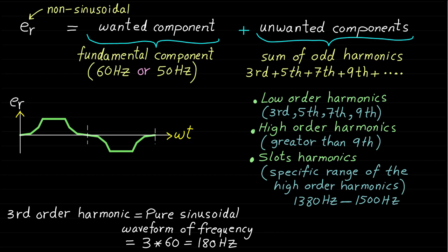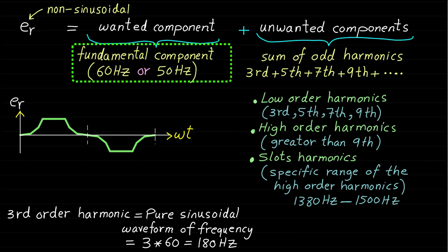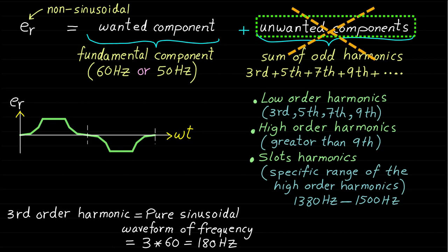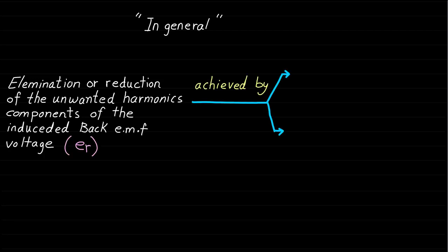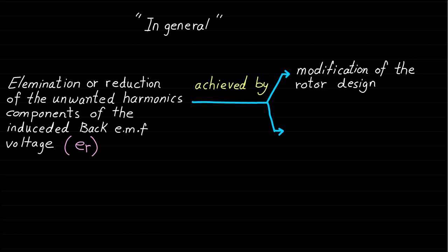We will give more detail about these harmonics during the discussion of the distributed windings. Now, pay attention to this important point. In practice, the armature back EMF induced voltage ER should ideally contain only the fundamental component with a frequency of 60 Hz or 50 Hz. Therefore, the unwanted harmonic components should be eliminated or reduced. In general, this elimination or reduction can be achieved by using two approaches. The first approach, or design freedom, is through modification of the rotor construction design. The second approach, or design freedom, is through the armature windings design.